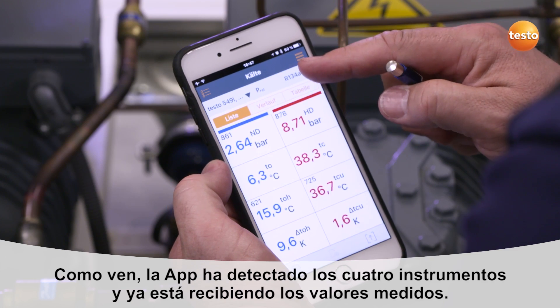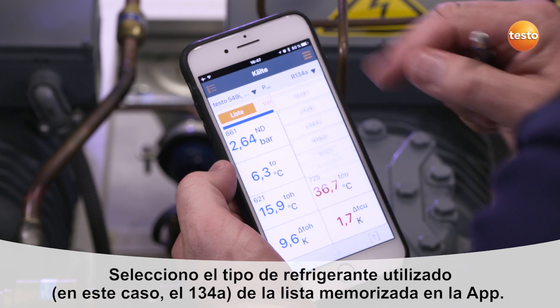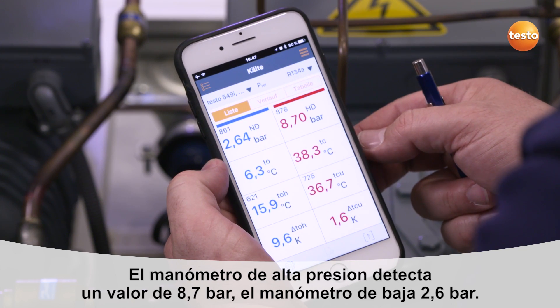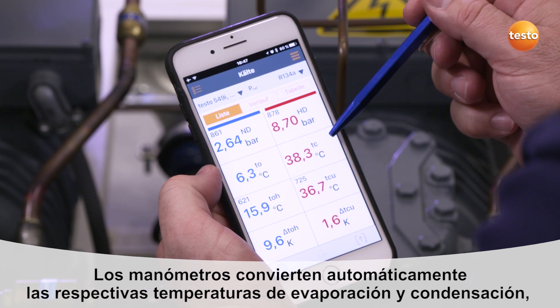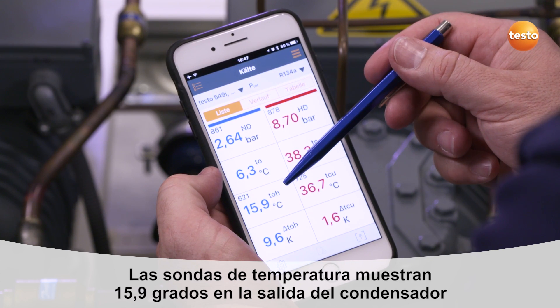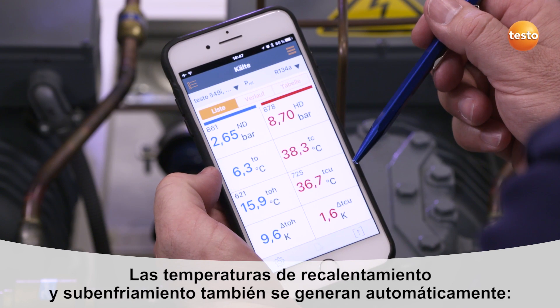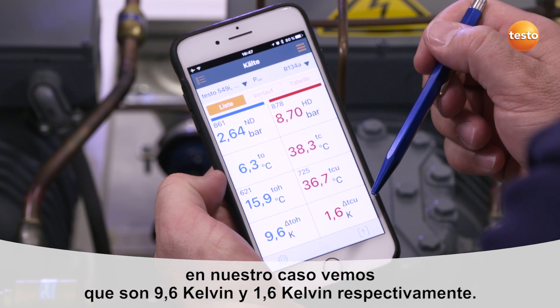Our four sensors are detected by the instrument. The first thing we can do is select the refrigerant used in the system — in our case it is R134A, which has already been preset. The high pressure probe reports a pressure of 8.7 bar, the low pressure probe 2.6 bar. The instrument automatically converts the respective evaporation and condensation temperatures, which we can then read directly. Both temperature probes report 15.9 degrees Celsius at the condenser outlet and 36.7 degrees Celsius in the liquid line. The corresponding evaporator superheating is also generated automatically — 9.6 Kelvin is indicated and a subcooling of the liquid line of 1.6 Kelvin.